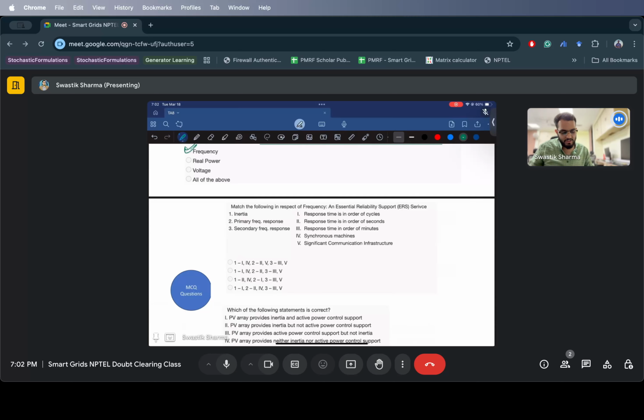Next, map inertia and other essential reliability support services with respect to frequency response. Inertia has a response time in the order of cycles, that's true. Within a few cycles this kicks in. It's not in the order of seconds or minutes. It's only applicable to synchronous machines, and it does not require significant communication infrastructure.